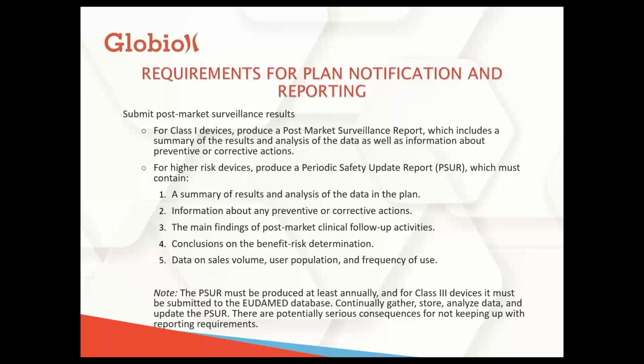And these are some of the things that it must contain: a summary of the results and analysis of data that's in the plan, information about preventive and corrective actions, of course, and the main findings of post-market clinical follow-up, if you've done those, and like Mike says, most often you will have to do them. And then the conclusions on the benefit-risk determination. That is the most important part of this, to determine if your device is still beneficial, who it's still beneficial to, and if there are any particular risks. So for instance, is there an age beyond which the risk becomes greater than the benefit? Is there a gender risk, for instance? Is there a risk based on body size? Those kinds of things are what you're trying to determine.